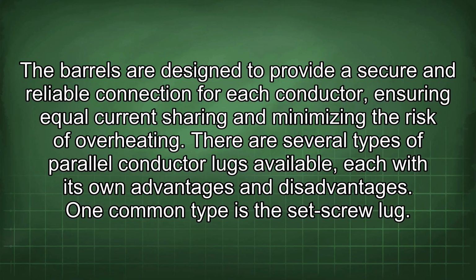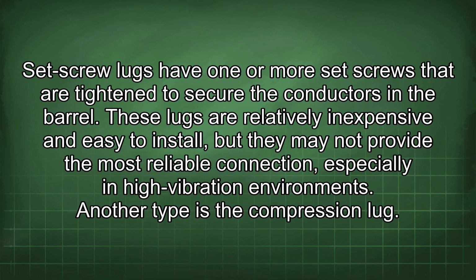One common type is the set screw lug. Set screw lugs have one or more set screws that are tightened to secure the conductors in the barrel. These lugs are relatively inexpensive and easy to install, but they may not provide the most reliable connection, especially in high vibration environments. Another type is the compression lug.